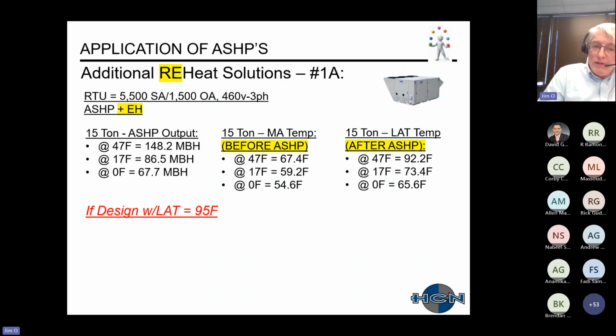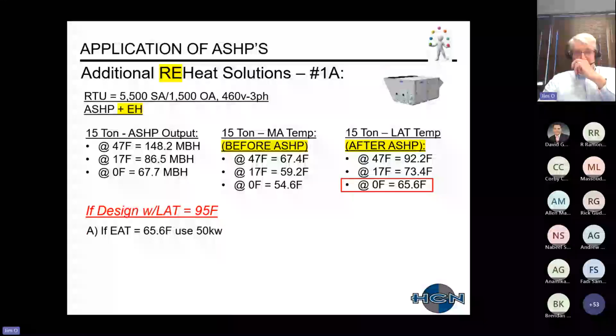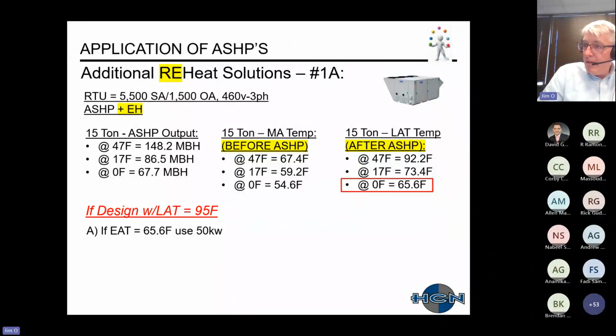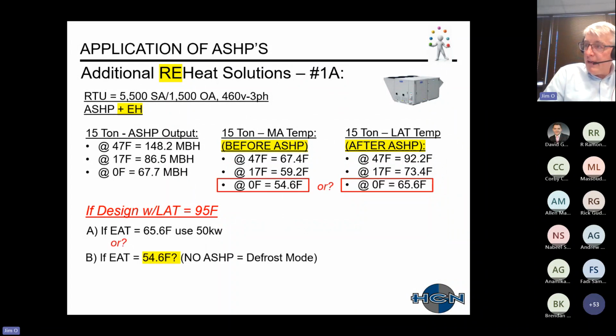All right, so we're going to assume a design with a leaving air temperature of 95. If I'm going to use 65 as my entering air temperature while the air source heat pump is operating, that comes out to a 50 kW heater. But then if I look at my heating operation with my air source heat pump not operating, in defrost mode, that turns into a larger heater.